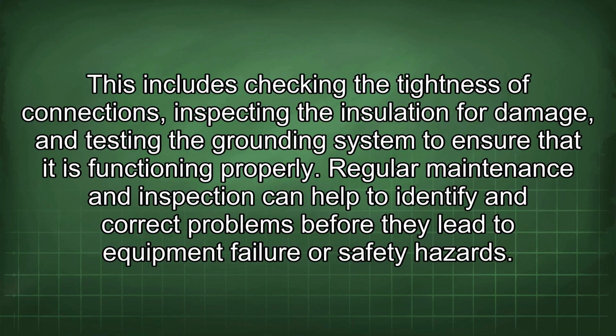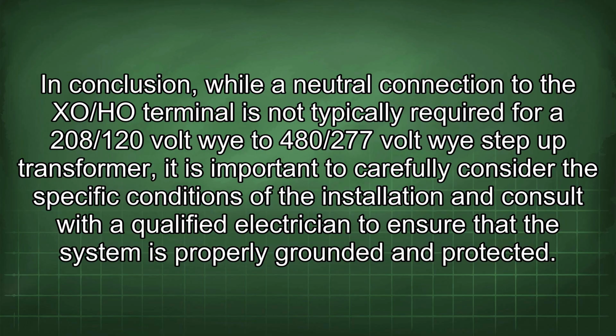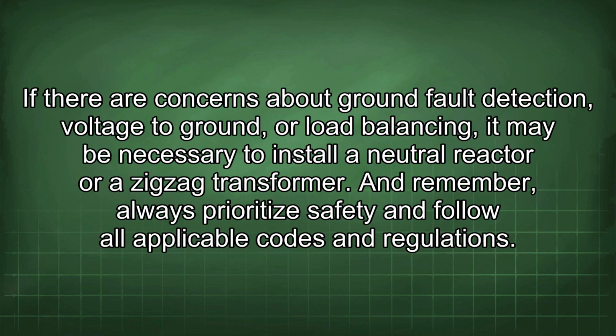Regular maintenance and inspection can help to identify and correct problems before they lead to equipment failure or safety hazards. In conclusion, while a neutral connection to the XO/HO terminal is not typically required for a 208/120 volt Y to 480/277 volt Y step-up transformer, it is important to carefully consider the specific conditions of the installation and consult with a qualified electrician to ensure that the system is properly grounded and protected. If there are concerns about ground fault detection, voltage to ground, or load balancing, it may be necessary to install a neutral reactor or a zigzag transformer. And remember, always prioritize safety and follow all applicable codes and regulations.